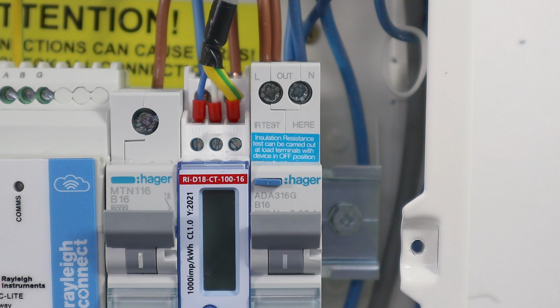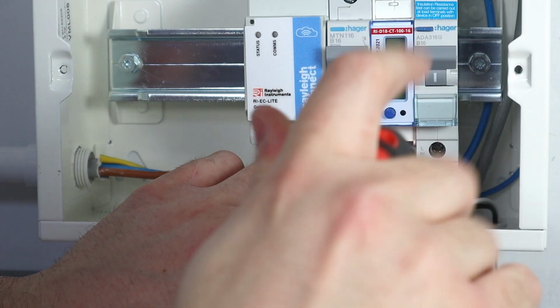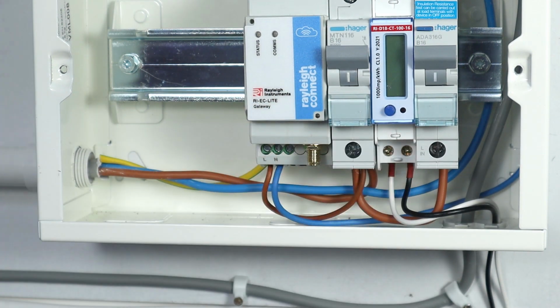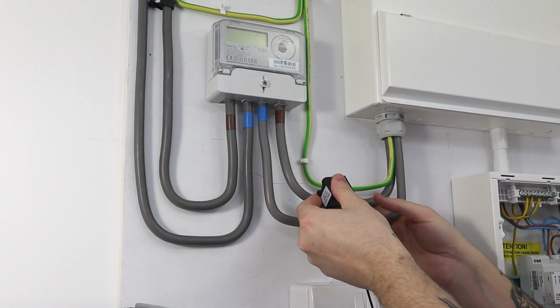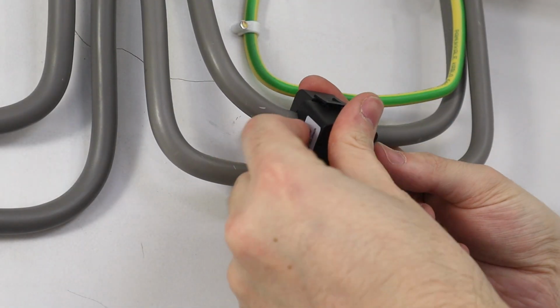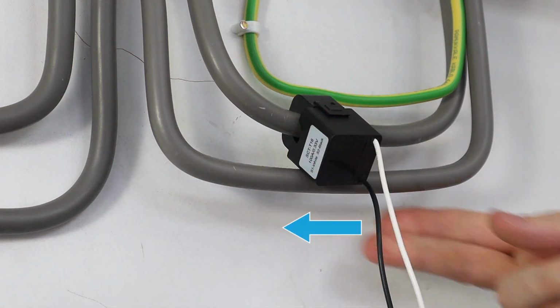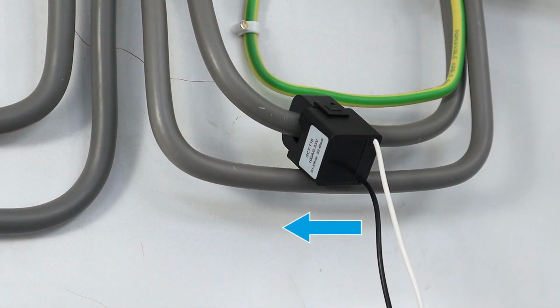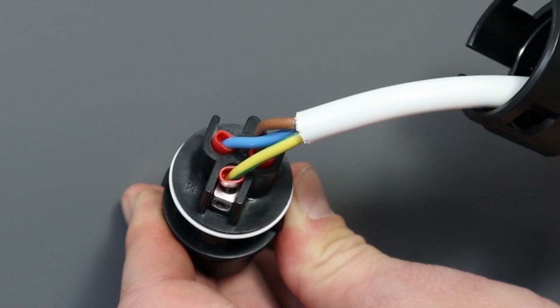To complete this method of measuring the energy usage, connect the white S1 positive lead and the black S2 negative lead from the current transformer to the meter. As before, clip the current transformer over the live mains incomer and ensure the arrow on the CT is pointing in the correct direction. For the AC connection, wire the AC connector plug with live, neutral and earth wires into the corresponding terminals.